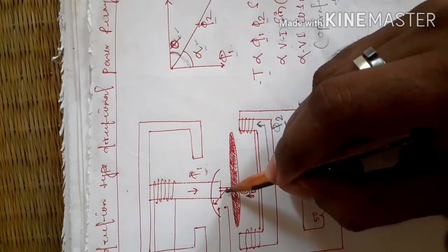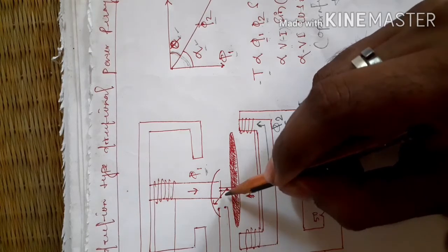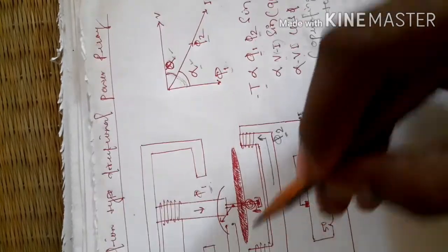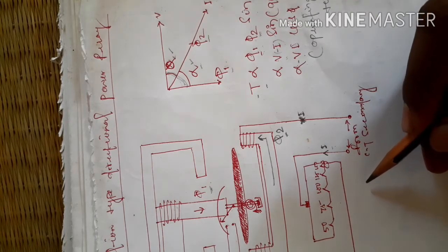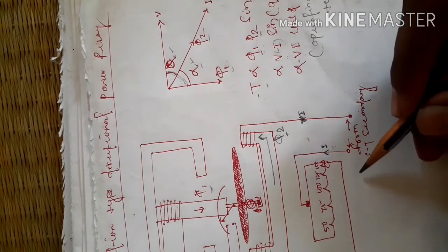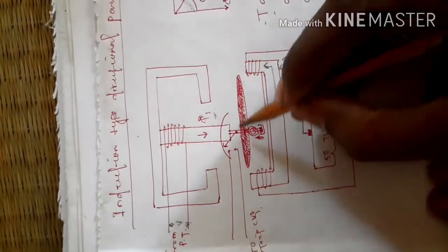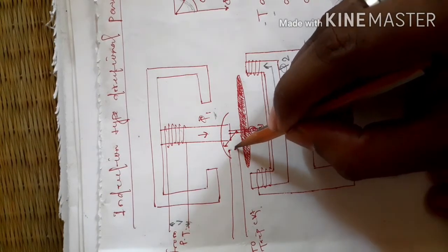If it is able to rotate in the reverse direction, then these two points are closed by this moving contact and the trip circuit is activated. When the operating torque is large enough as compared to the restraining torque, the disc rotates in the reverse direction and the moving contact closes the trip circuit.